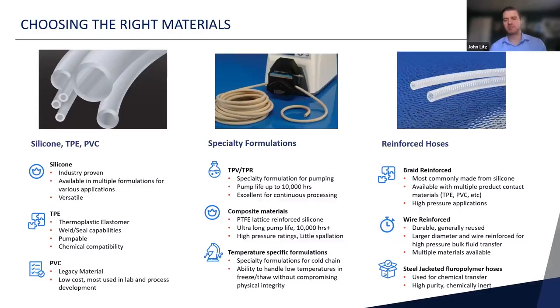Whereas you might see a braided hose with an ID anywhere from an inch to an inch and a half, wire reinforced hoses might go anywhere from 4 inches, even all the way up to 6 inches in some cases. But these generally aren't going to be considered single use—in most cases you're going to be autoclaving the hoses after initial use and then reusing them in process.